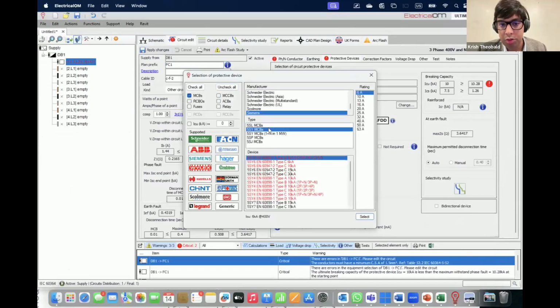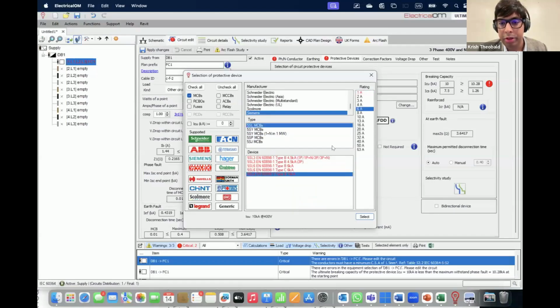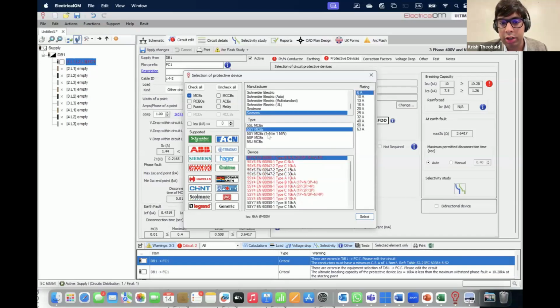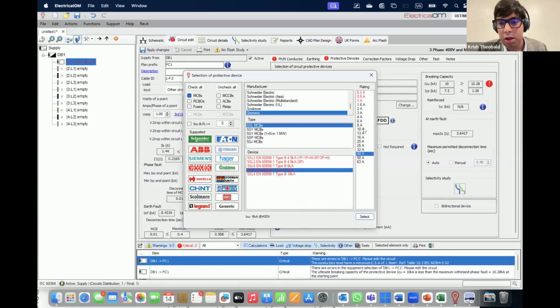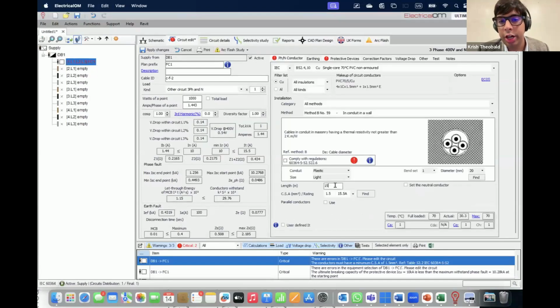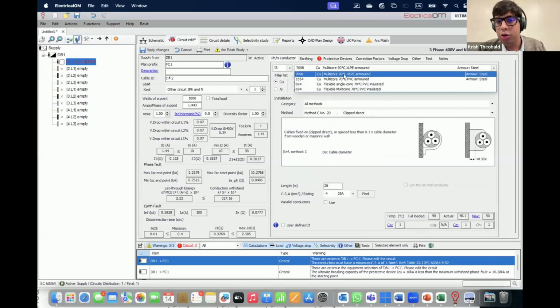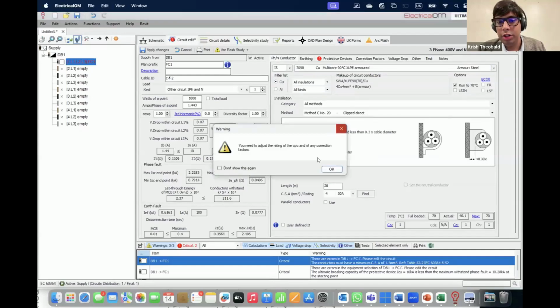So say, for example, it's the 5SY series, or the 5SL, let's keep it simple. Say it's a type B in this case, or actually, for a drilling machine we will take a slightly different device. Let's take it as type C10. Actually, hold on one moment, please. Yeah. Now, let's say that this run, let's say the run was 20 meters. So the cable is actually running 20 meters. And again, Indian standard, copper, multi-core, so IS 7098, we'll run it to 70.